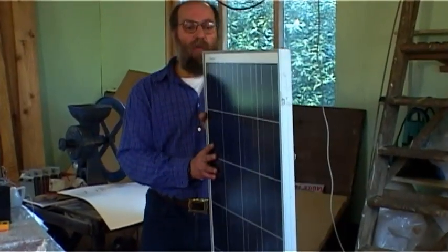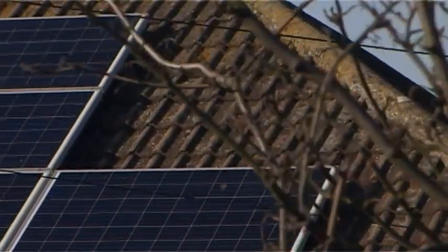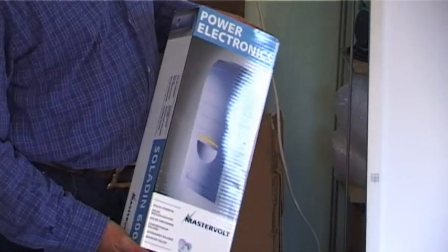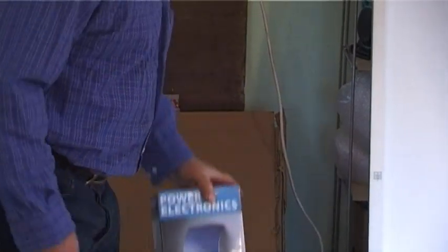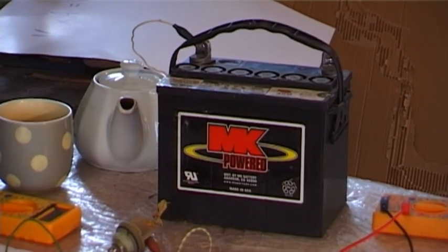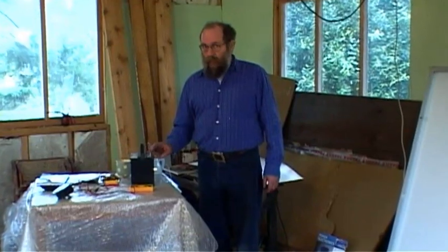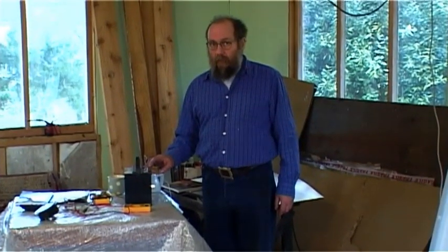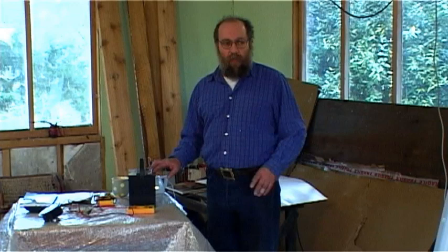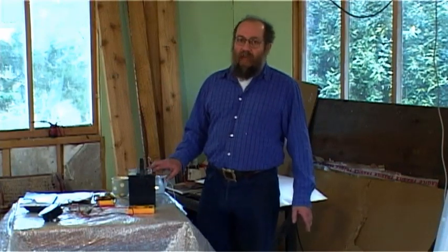So that's the solar panel. We have a solar panel, or a series of them, going to a battery or to a grid-tie inverter — we'll have a look at the inverter later on. Between the battery and the panels we have to have one or two components. We can have a diode called a blocking diode, which means that when the sun has gone down, there is no possibility of any power going from the battery back into the panels — it can't back-feed. The other thing you need is a charge controller.